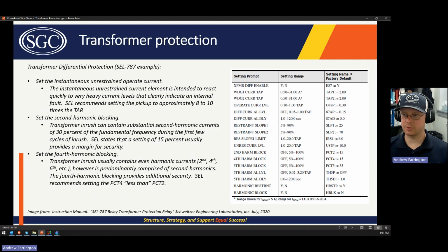The harmonic blockings, these are really important. I wish I had more time to talk about them. The second harmonic blocking is usually on inrush current. So the first few cycles, because the transformer core is basically a big magnet. You've got the flux flowing around in there, right? And then say the transformer is in operation, and then you open the breakers and take it out of operation. Well, whatever flux was in the core when you opened it up is going to remain there. So it's basically a permanent magnet at that point.